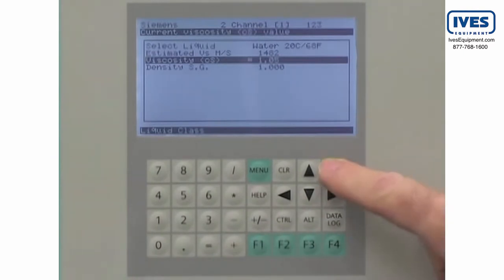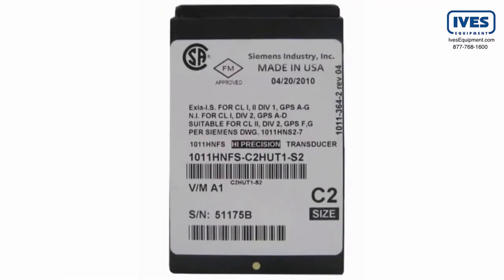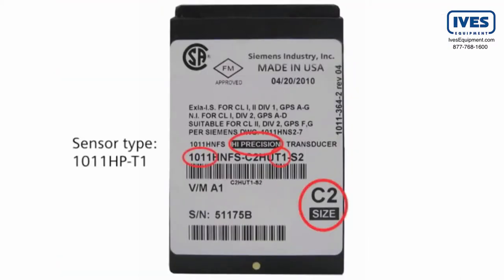Press the enter key to save your selection. Now we will enter the sensor data into the SITRANS FUS1010. This will help us mount the sensors for optimal performance. The data we need is the sensor type and size, found on the sensor label. Since the sensors are supplied as a matched pair, verify that they have the same serial number, followed by an A or B.